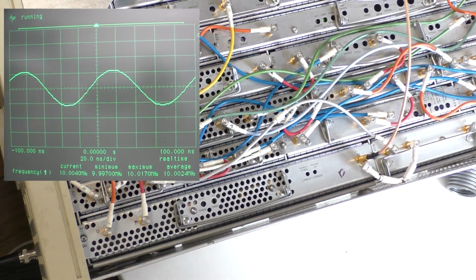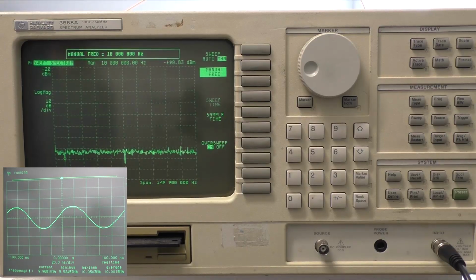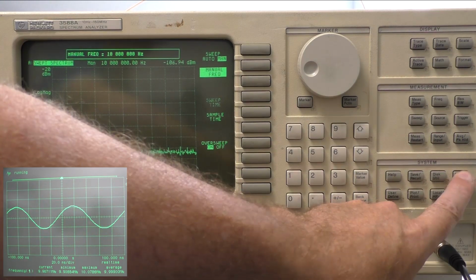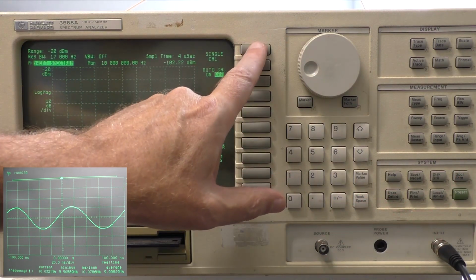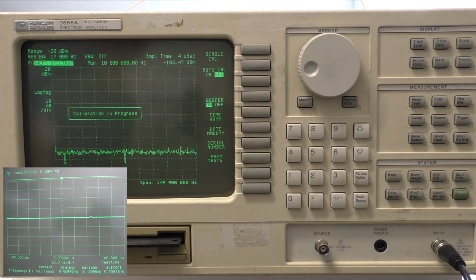You may or may not see the 10 MHz waveform on the oscilloscope. In our case, we see the waveform. Whether or not you see the waveform, we want to run a calibration during this monitoring. We have noticed an anomaly after performing a calibration. Do the following. Hit special function. Single calibration. The waveform will disappear as the self-test inserts its own signal into the input. At the end of the calibration, the self-test should restore the generator's signal and you should see the waveform on the oscilloscope. In our case, the signal is absent.